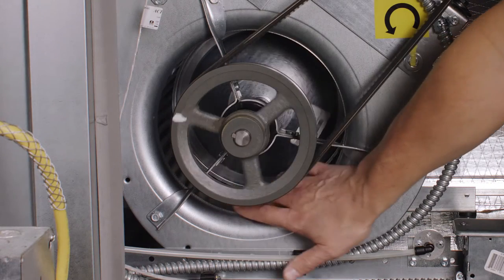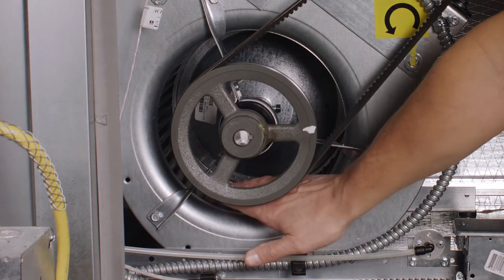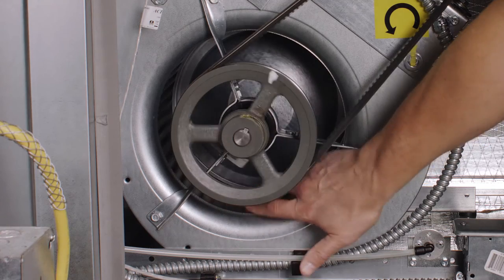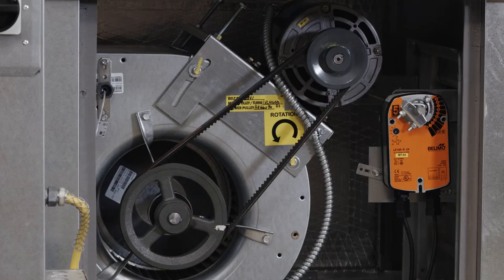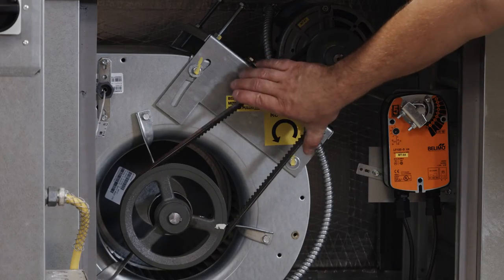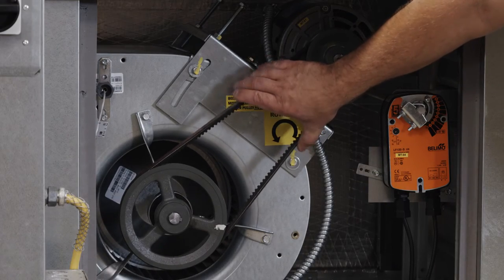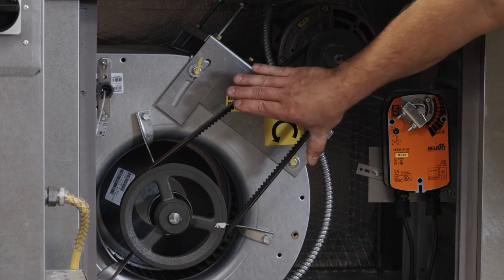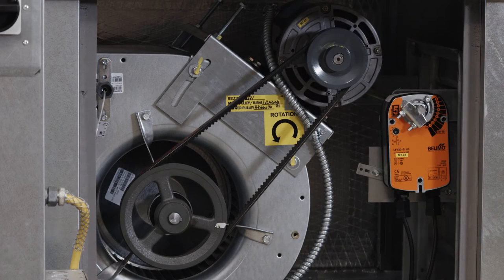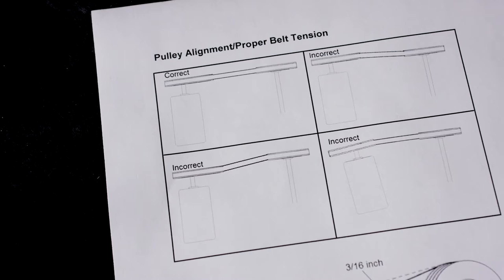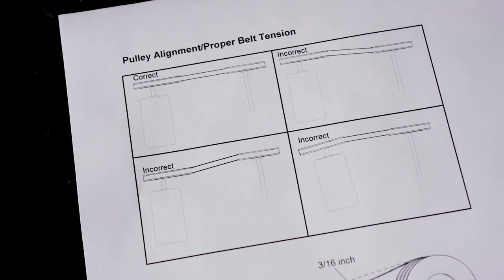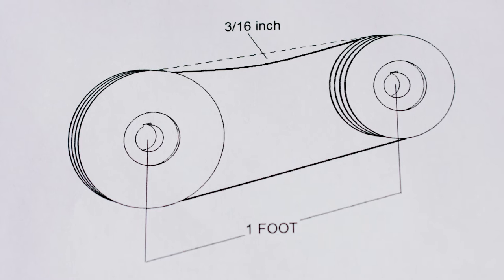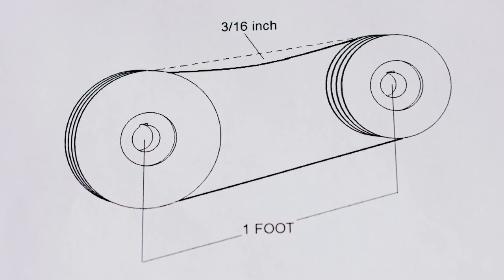With the power off, turn the wheel by hand to ensure it spins freely. This is also a good time to ensure your pulleys are aligned and the belt tension is correct. Refer to your operation and installation manual for belt tension specifications.